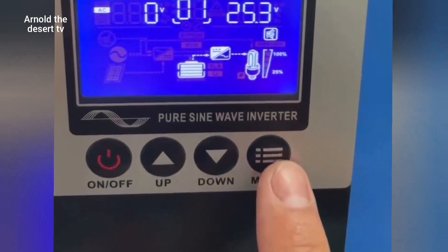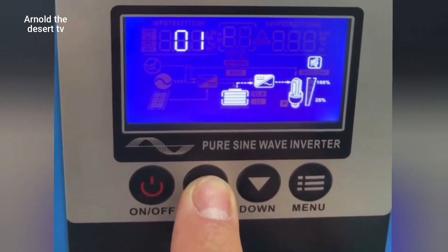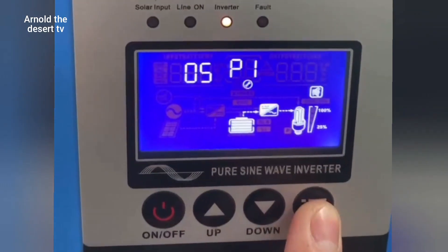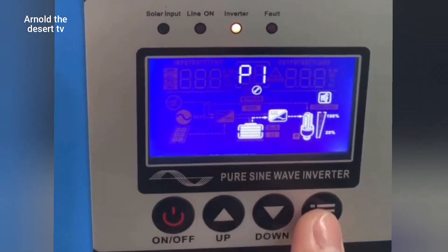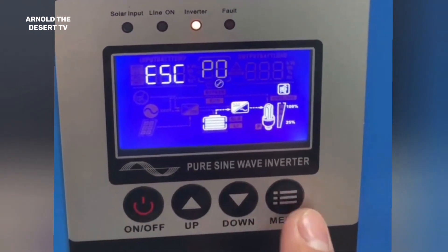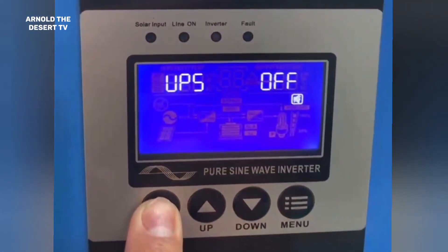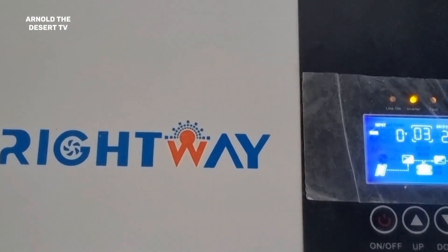Press the menu button 3 to 5 seconds. Select P1 using the up and down button. Press again the menu button to adjust from 01 to 03, which is the 3 batteries connected, using again the up and down button. Press the up and down button to select ESC, then press the power button up to 3 seconds to save the program. Turn on again the inverter by long press. Now the 1 has become 3 — 3 means 3 batteries connected to this inverter.